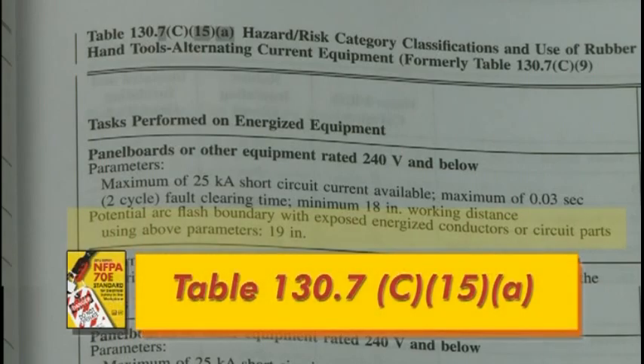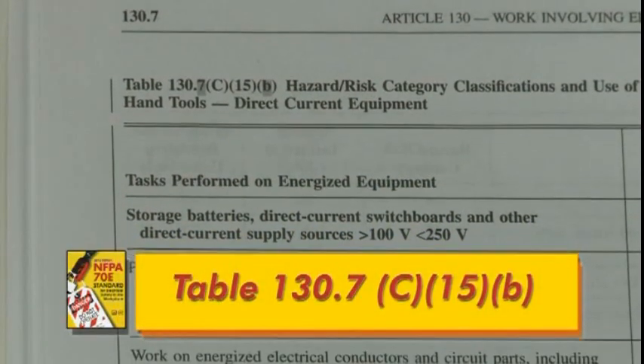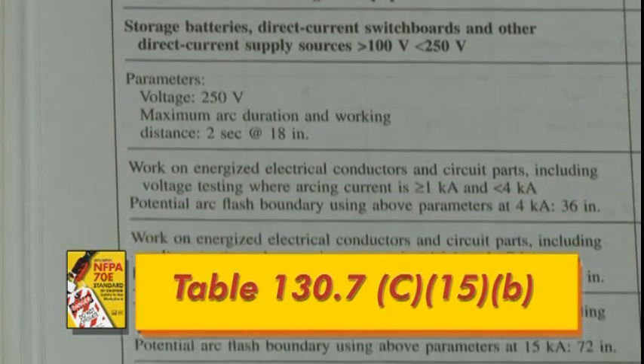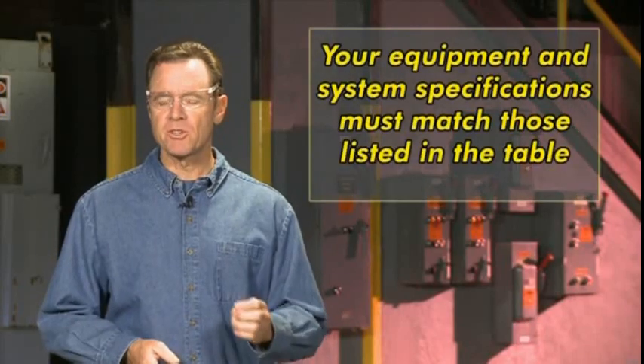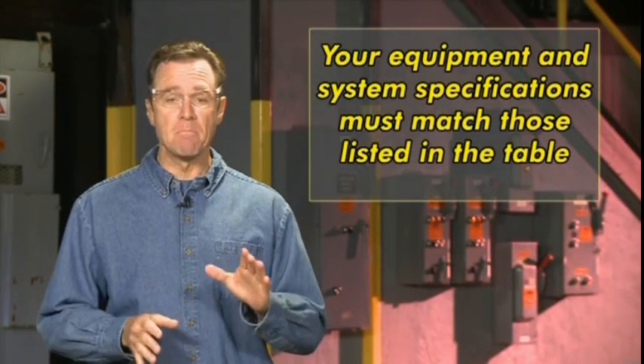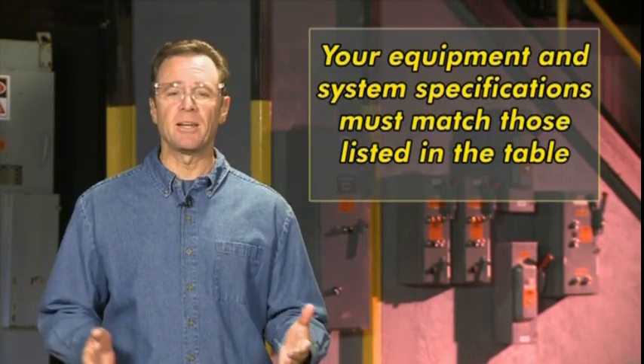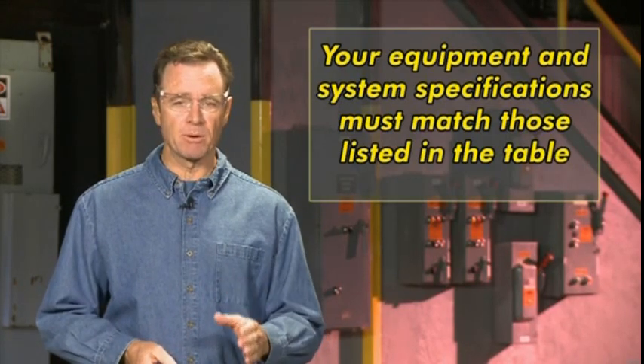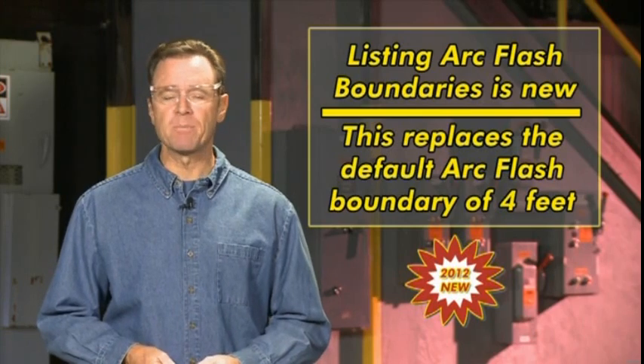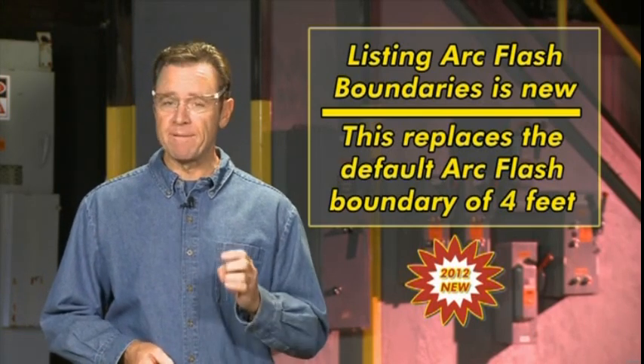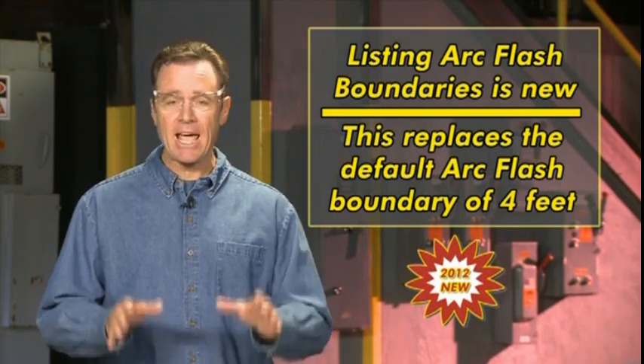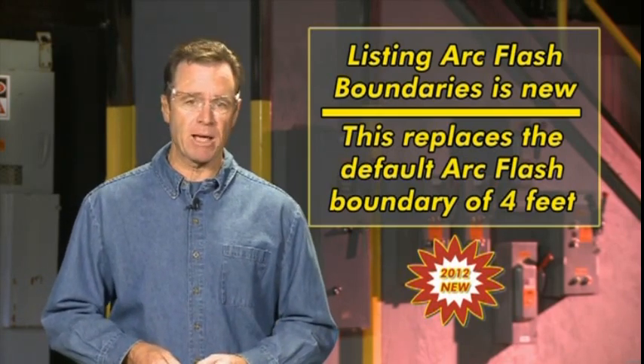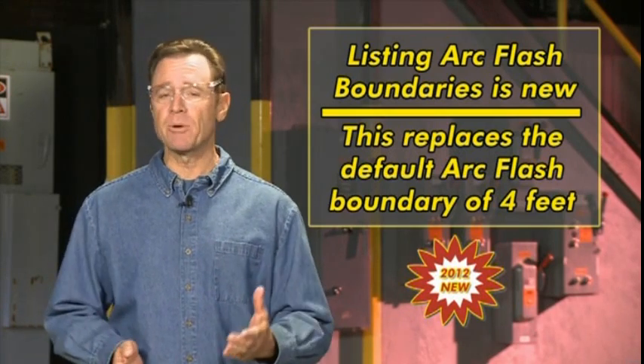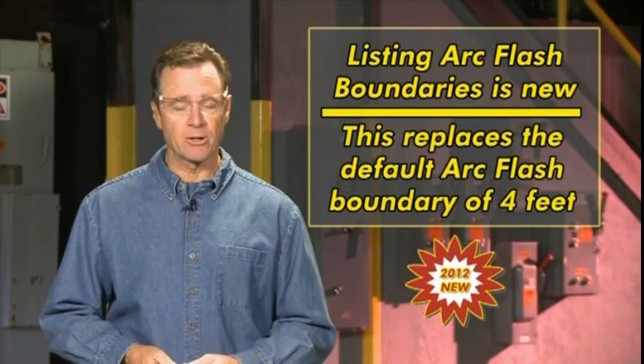This information is contained in Table 130.7 C15A for AC systems and Table 130.7 C15B for DC systems. Before using this information, you must ensure that your equipment and system specification match those listed in the table. If they do not, an appropriate arc flash analysis must be performed to determine the arc flash boundary. Listing arc flash boundaries in Table 130.7 C15 is a major revision to the 2012 NFPA and replaces the default arc flash protection boundary of 4 feet, which was defined by prior editions of the NFPA for conforming electrical systems.